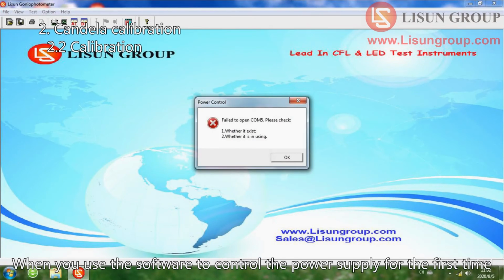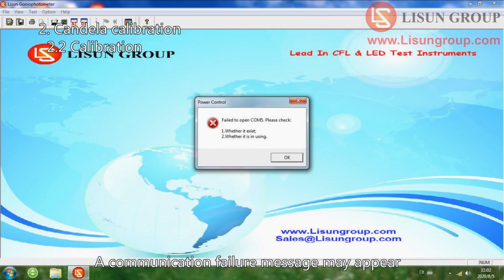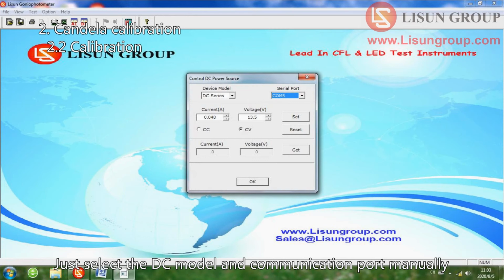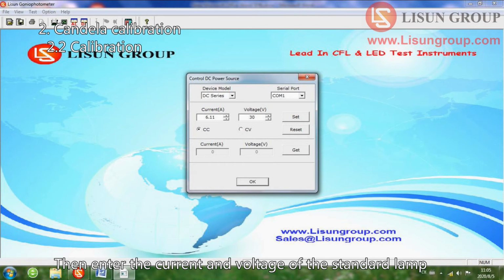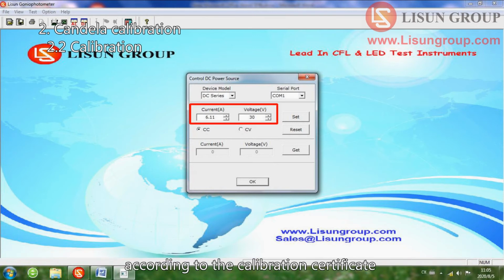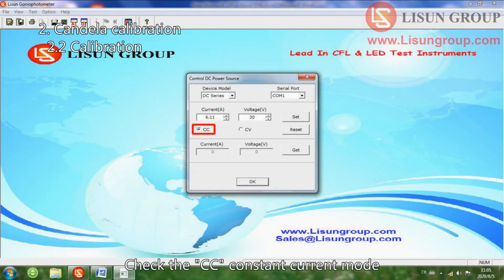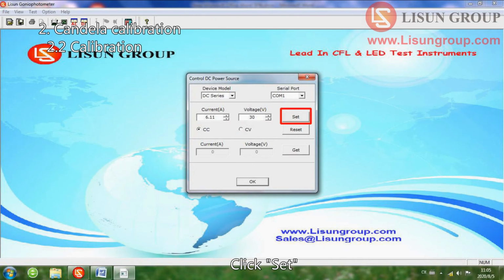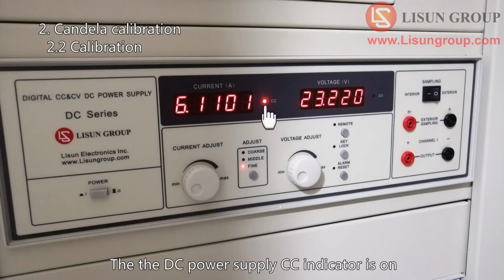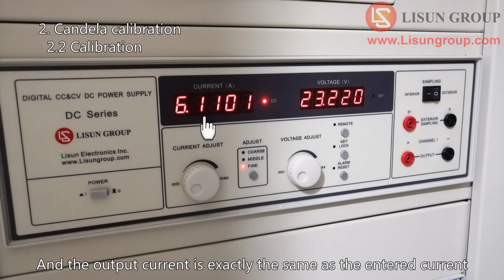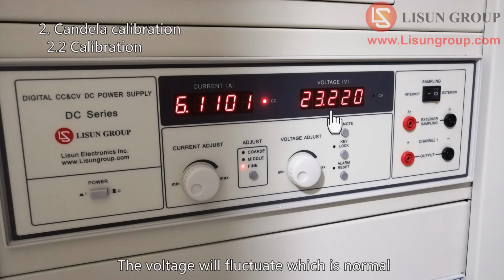When you use the software to control the power supply for the first time, a communication failure message may appear. Just select the DC model and communication port manually. Then enter the current and voltage of the standard lamp according to the calibration certificate. Check the CC constant current mode. Click Set. The DC power supply CC indicator is on, and the output current is exactly the same as the entered current. The voltage will fluctuate, which is normal.